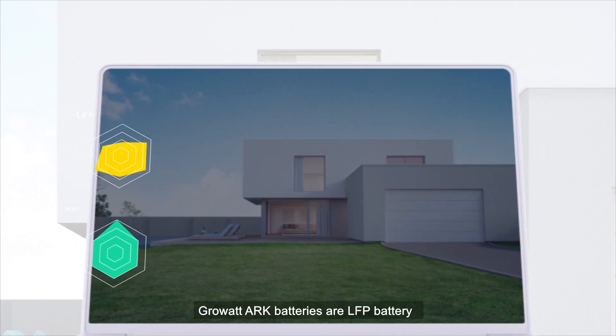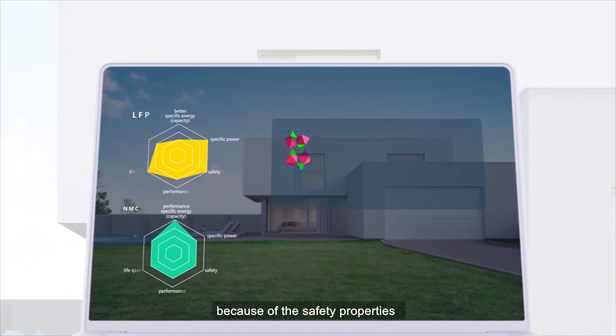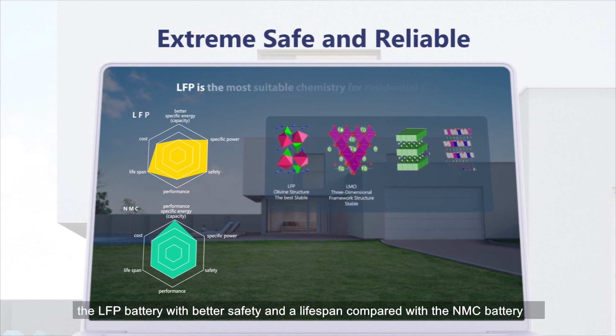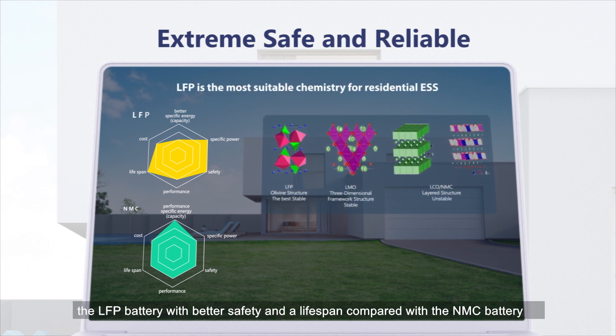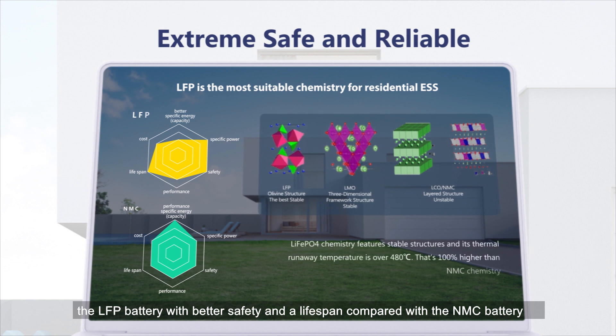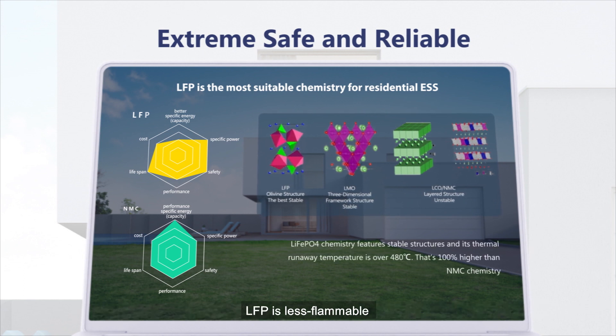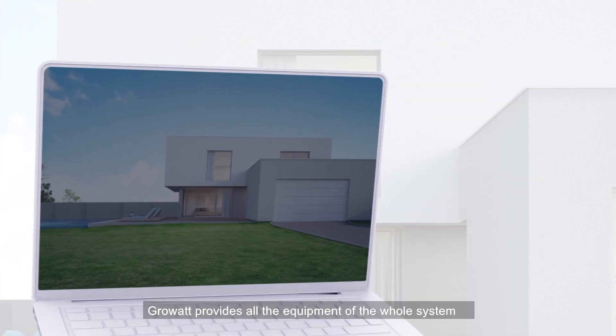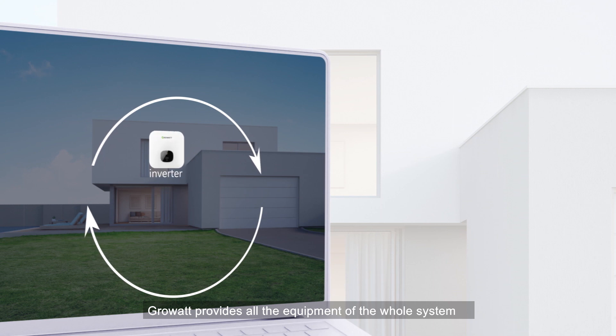Growatt ARK batteries are LFP batteries. Because of their safety properties, LFP batteries offer better safety and lifespan compared with NMC batteries. LFP is less flammable, the chemistry features a stable structure, and the thermal runaway temperature is much higher than NMC.